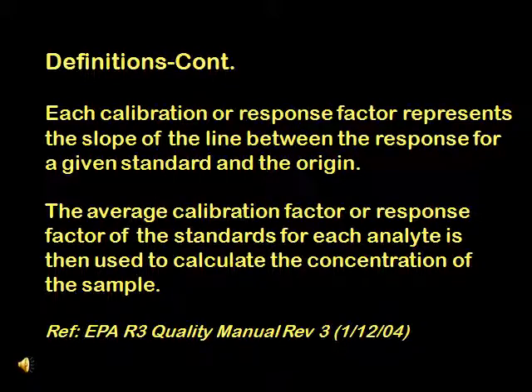Each calibration or response factor represents the slope of the line between the response for a given standard and the origin. The average calibration factor or response factor of the standards for each analyte is then used to calculate the concentration of the sample.